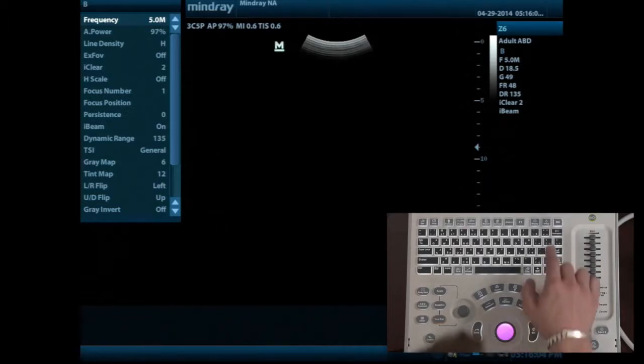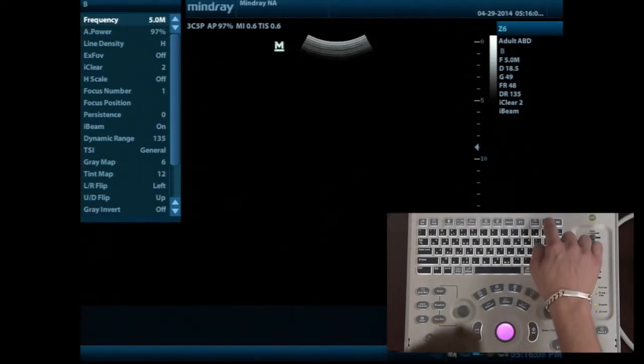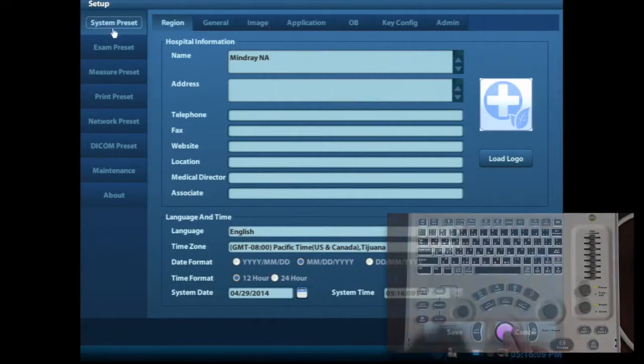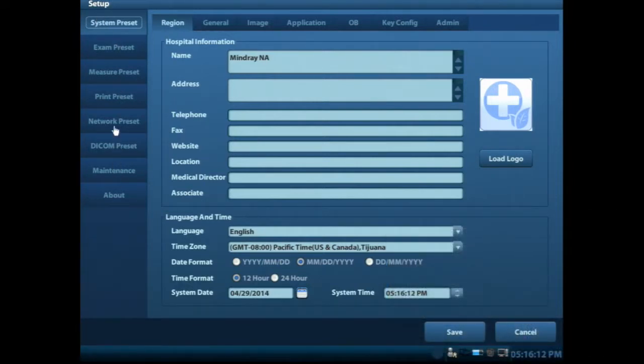This is where we're going to want to choose the setup button, which is located toward the top of the keyboard. When I press that, it'll give me a menu on the left-hand side, and it'll also give me some tabs across the top depending on which setup tab I'm in. This first one is important as you set up your new equipment. This system preset gives you the region tab, where you can put in your facility name, address, telephone number, as much as you'd like. You can choose your time zone, you can choose the date format, as well as 12-hour versus 24-hour. The system date, make sure is accurate, and then you can have your time change if you need to.